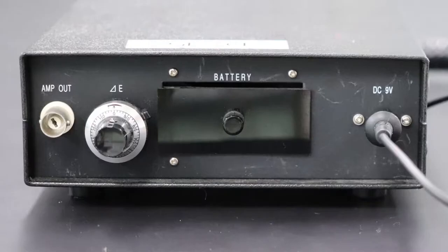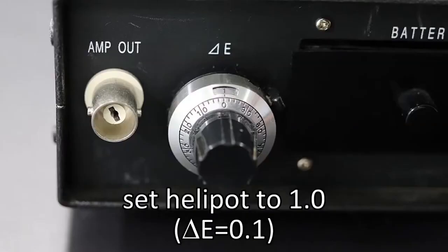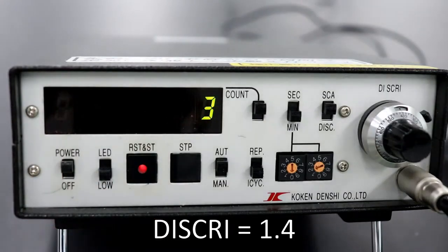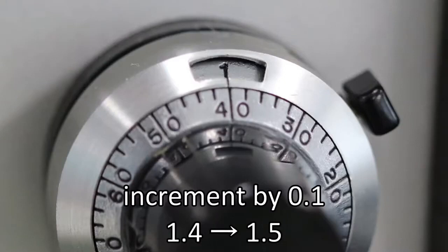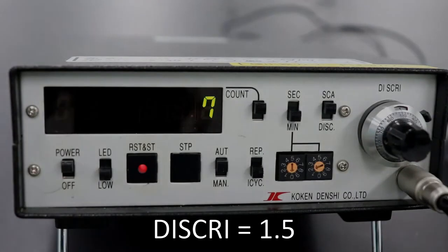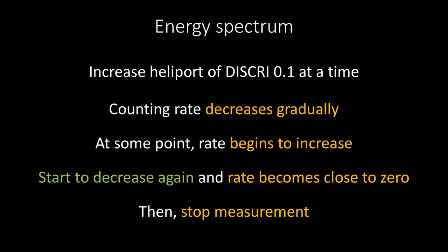Set the delta E setting. The delta E setting is made at the helipot on the back of the detector control unit. Set it to 1.0. Delta E is now set to 0.1. Press the start button to start the measurement. After each measurement, increase the helipot's value by 0.1. Increase the value of DISCRI by 0.1, and repeat the measurement.